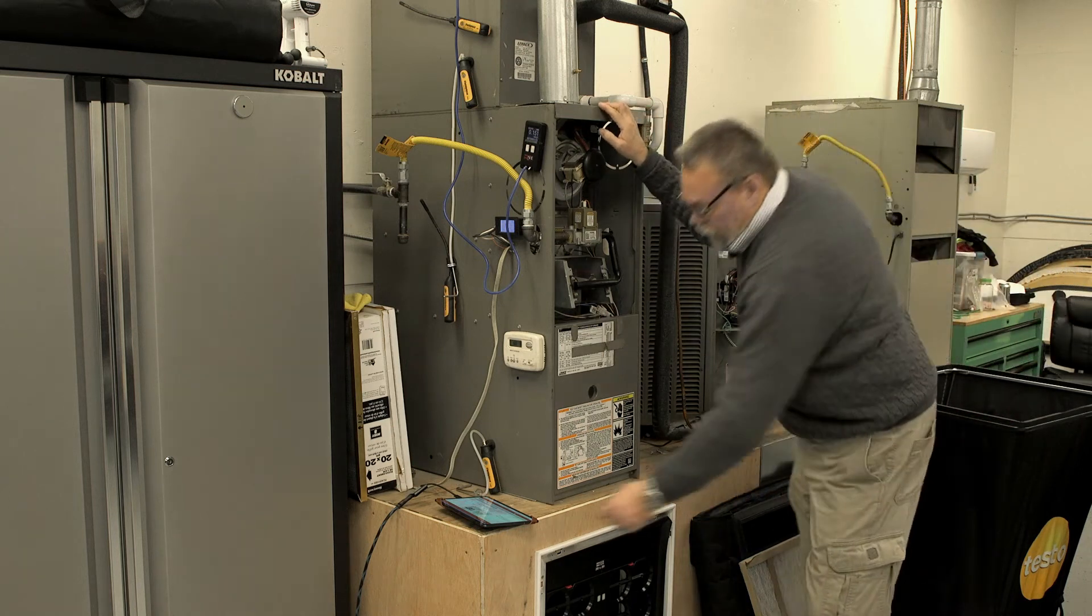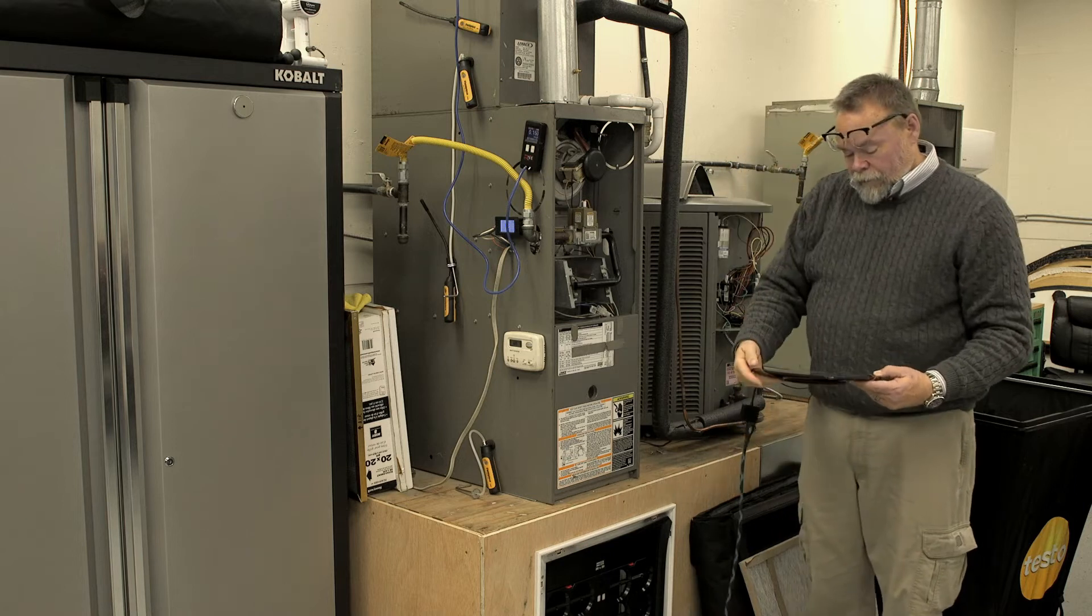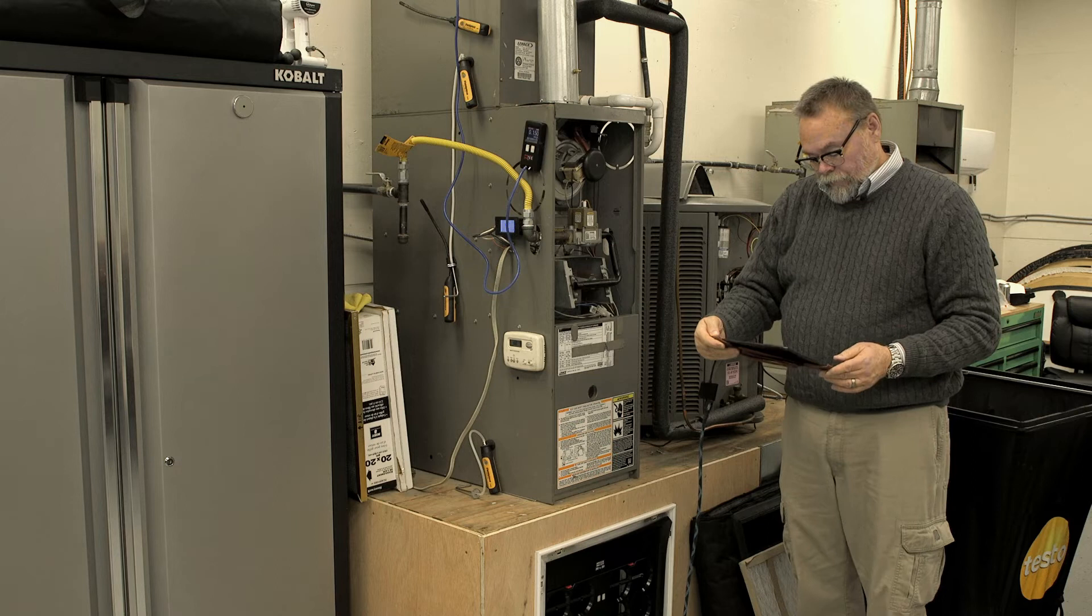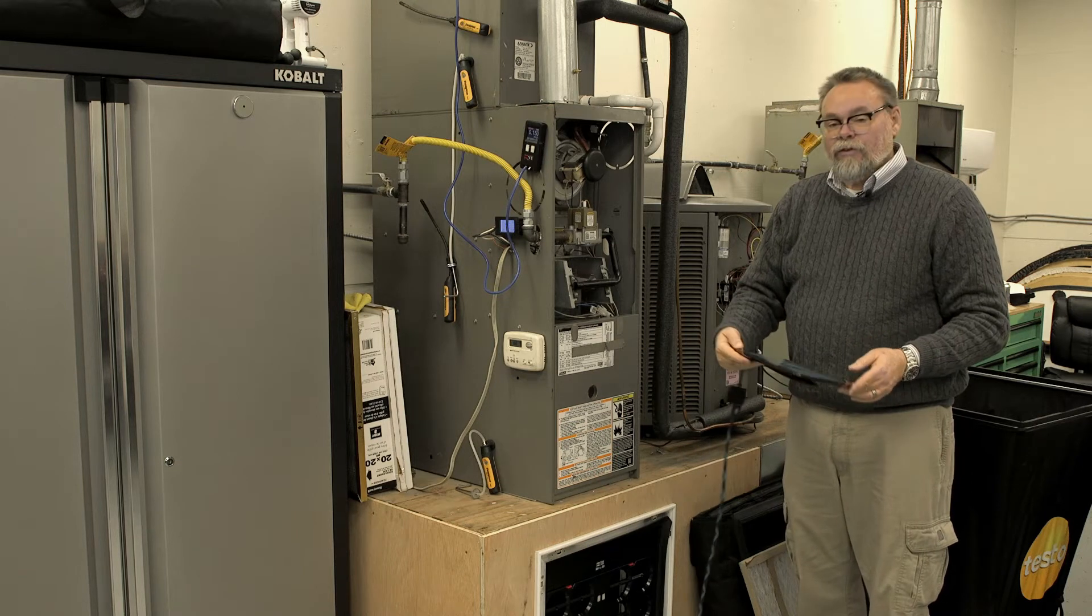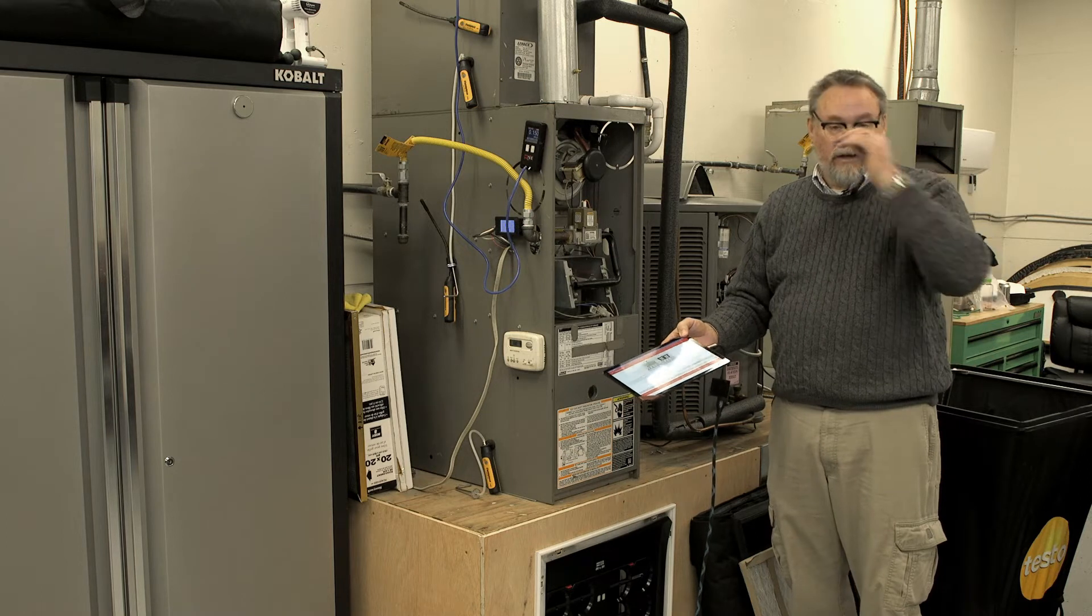What did we say the last one was? 655 or 658? What's our airflow going to come out to on this one? Probably going to be very close to it. Yeah, it said 658 CFM, but that was exactly what we were using when we did the test the other day.